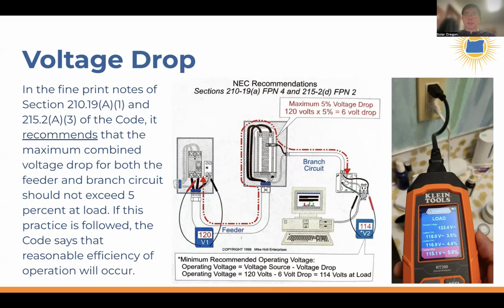The reason this isn't a requirement is because if you plug in, say, an electric resistance space heater, and you get voltage drop from that load, then instead of putting out what it's rated for -- let's say the space heater is rated for 1500 watts -- if it gets less voltage, it just won't produce 1500 watts. It might only produce like 1200 watts.